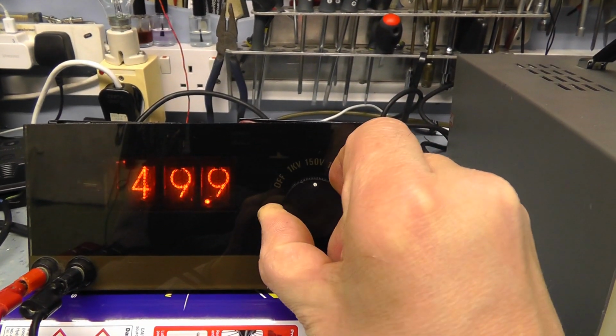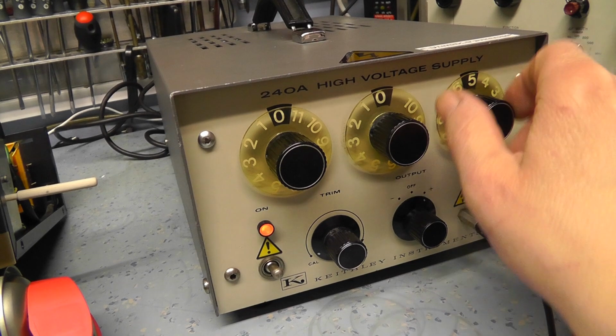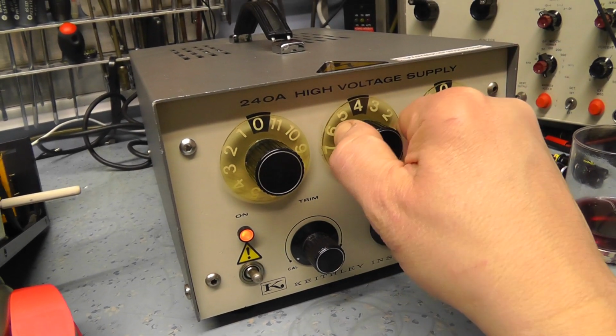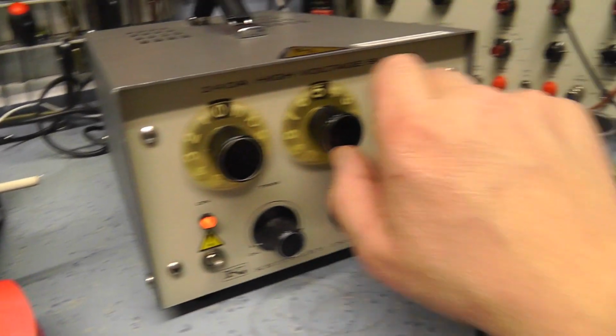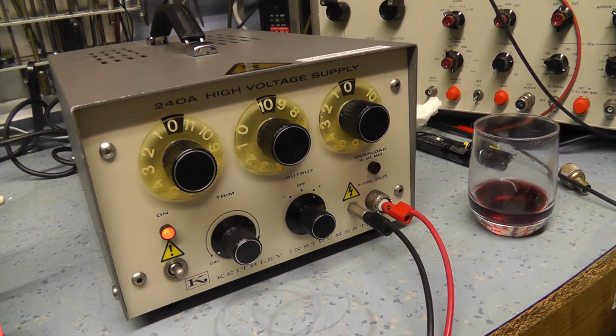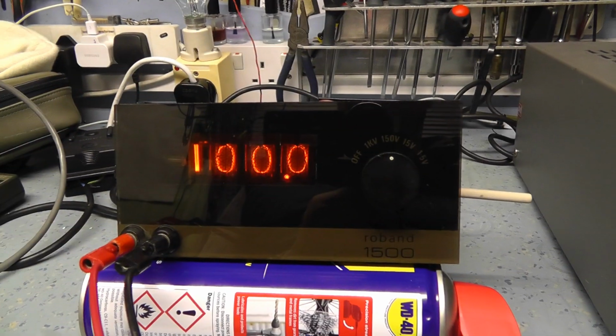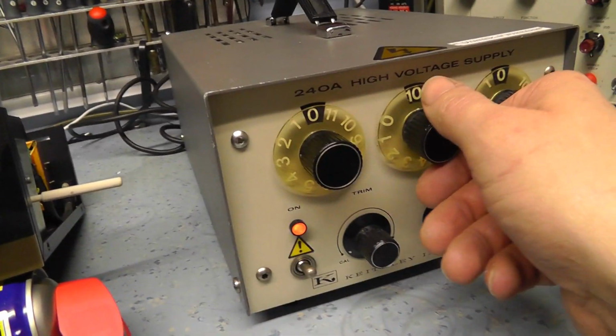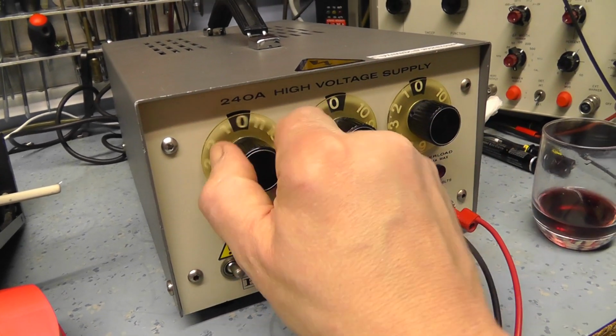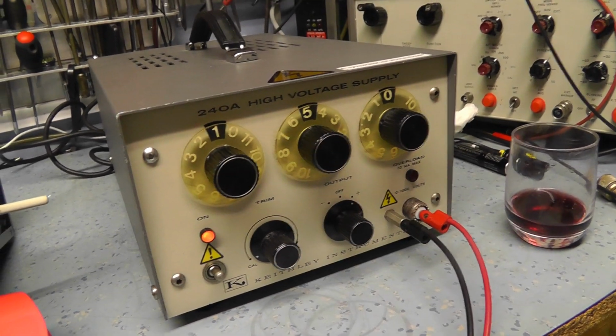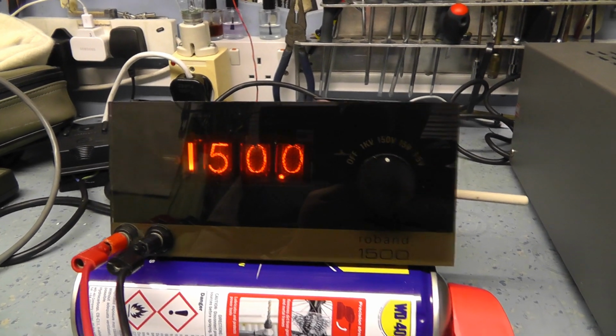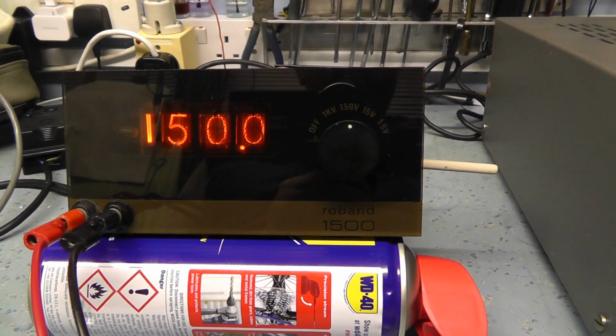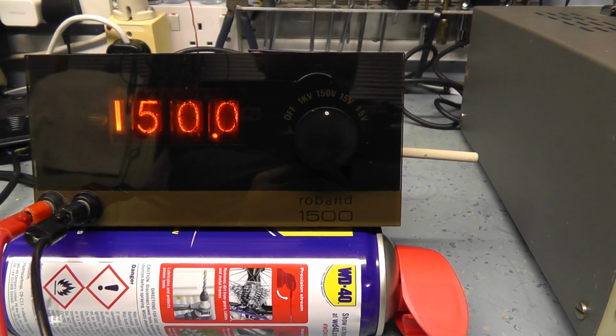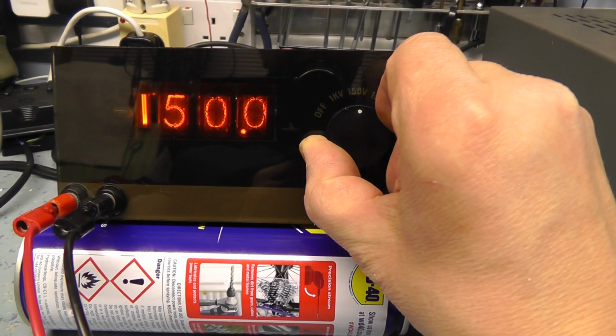4.99, that's good. Okay, so we change the range to the 150 volt range. So we'll go to 50 volts. That's good. 100 volts. Perfect. Let's go 150 volts. Let's do this another way. 150. That's the top of the limit of the range of this meter on this scale. So we'll go to the 1 kV range. So it should be 150 volts.